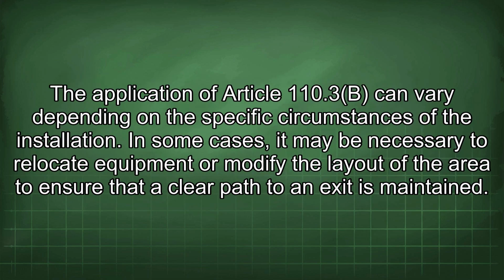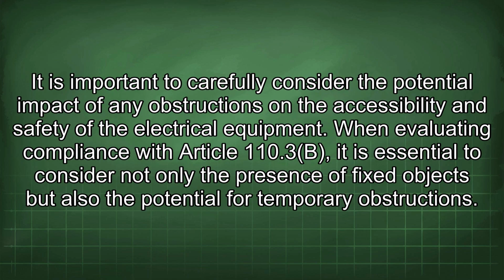The application of Article 110.3b can vary depending on the specific circumstances of the installation. In some cases, it may be necessary to relocate equipment or modify the layout of the area to ensure that a clear path to an exit is maintained. It is important to carefully consider the potential impact of any obstructions on the accessibility and safety of the electrical equipment. When evaluating compliance with Article 110.3b, it is essential to consider not only the presence of fixed objects but also the potential for temporary obstructions.